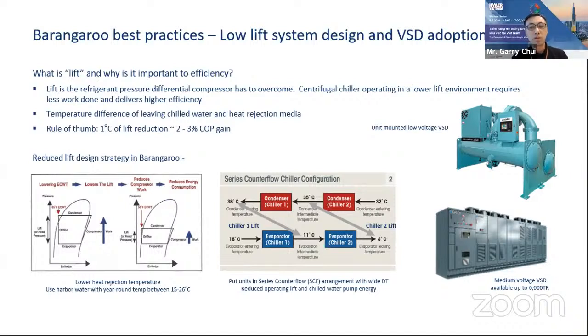For centrifugal compressors, if we are able to create lower lift design conditions for the machine to operate, that means it has less work to do and is able to deliver a higher energy efficiency. Logically, the lift is the pressure differential between the cooling side, which is the evaporator, and the heat rejection side, the condenser. What we try to look into is what we can do to narrow down this differential, by either raising the chill water temperature on the evaporator, or lowering the heat rejection temperature, which is what Barangaroo has done.